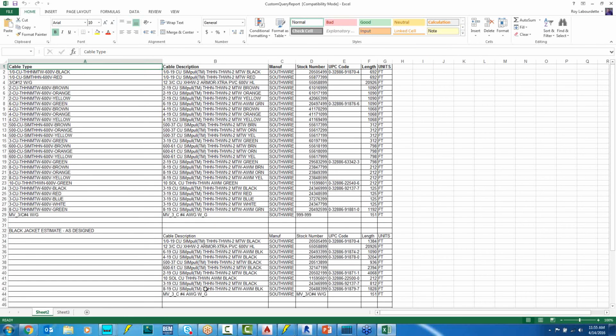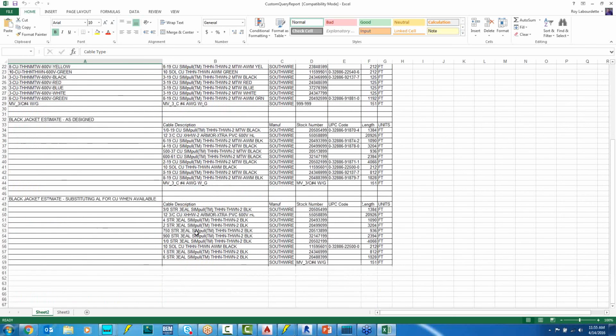So if we were going to buy all black jacket and then color code with tape at the end, I don't have to add up all the numbers - the program does that for me. Additionally, where aluminum conductors are available to substitute, it will swap out the copper for an aluminum equivalent with the same ampacity, and if you choose the aluminum alternative, the program will readjust your conduit sizes based on the larger diameters of the aluminum cable, as well as recalculate your tray fill percentage based on the larger diameter conductors.